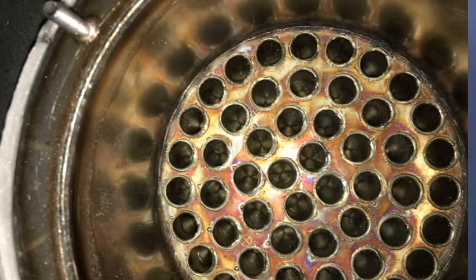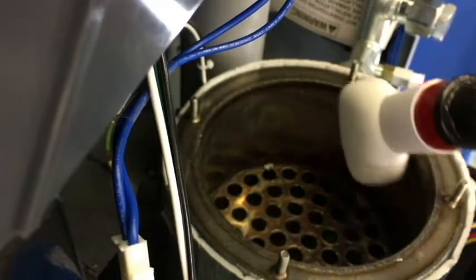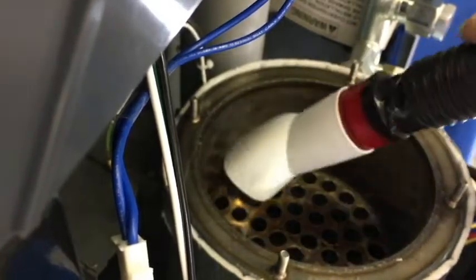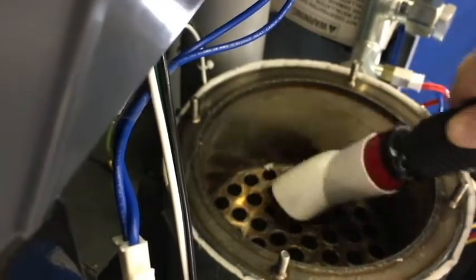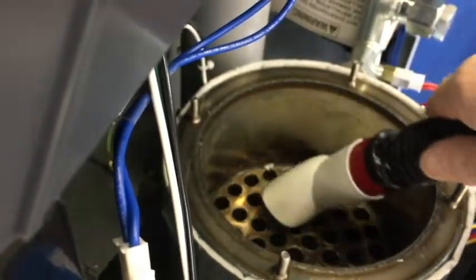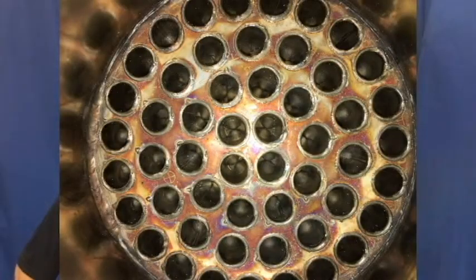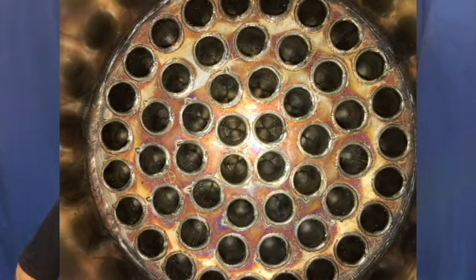If vacuuming does not remove all the debris, remove the control module then wash the heating surfaces with warm water and rinse with warm water. Never use any type of solvent or cleaner. Rinse the condensate trap with warm water.